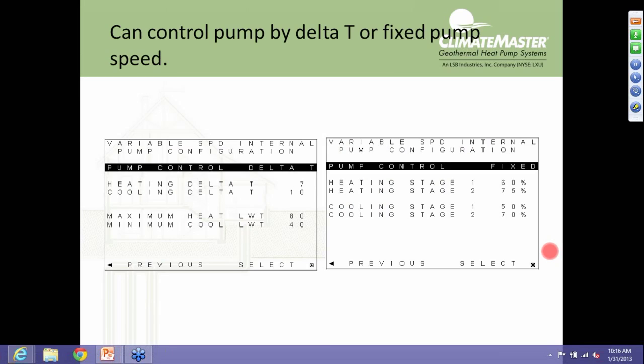Whereas delta T, there's some things going on in the background that we adjust the pump for. For instance, we'll get to here in a moment, in the heating mode, if the entering water temperature drops below 40 degrees, we automatically reduce the delta T, increasing the speed of the pump.